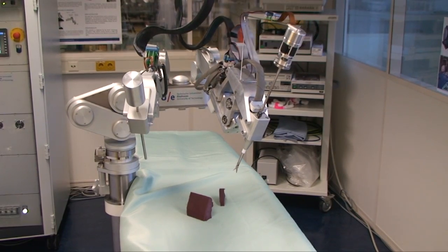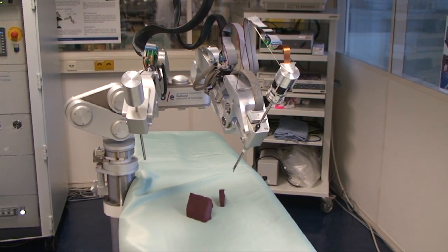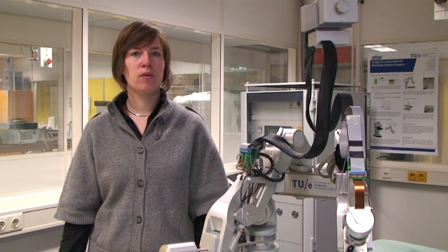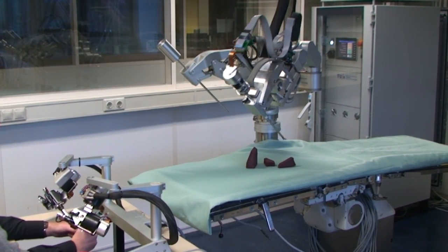The research focused on realization of the slave, the part of the robot that actually performs surgery at the operating table. A compact operating table-connected slave was developed, providing surgeons with the freedom to approach and feel the operative site. Attaching the slave to the table provides the possibility, for example, to reposition the intestine by rotating the table with the patient without the need to uncouple the robot. It enables easy setup, contact with team members, a good overview of the patient, and offers advantages for accurate instrument movements and good force measurements.